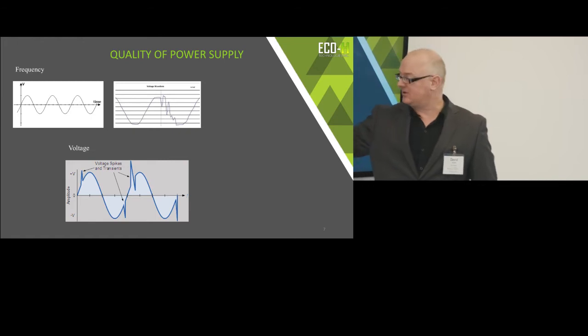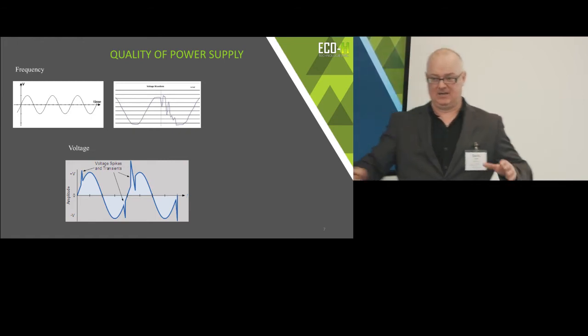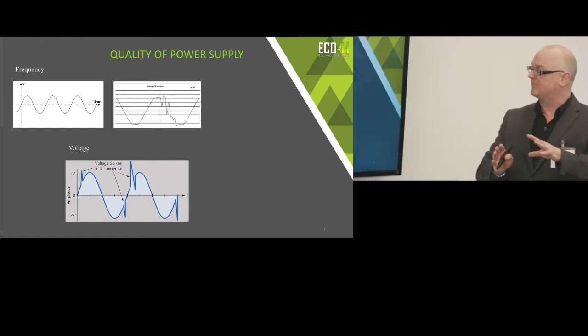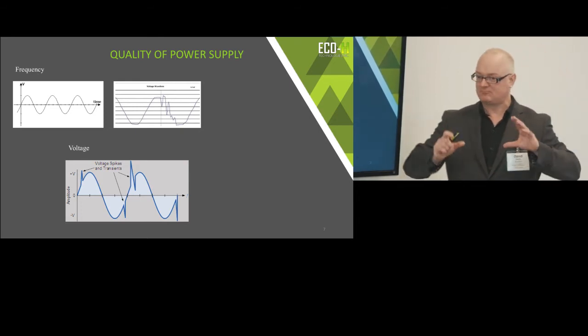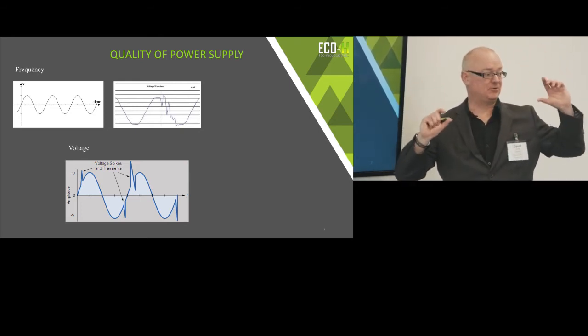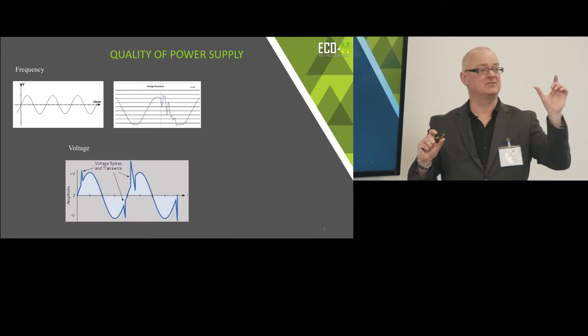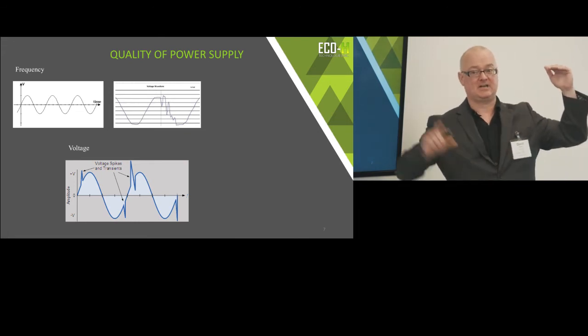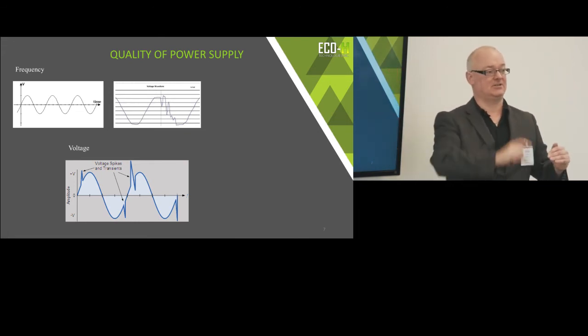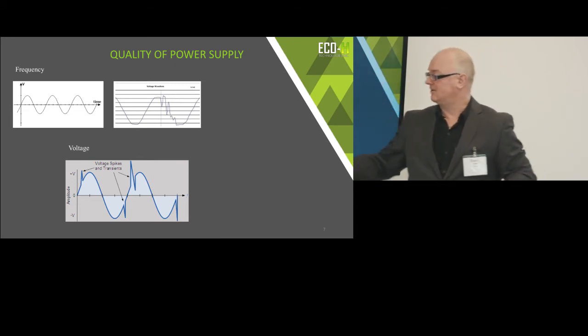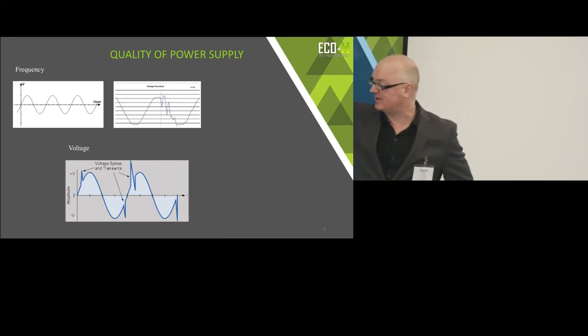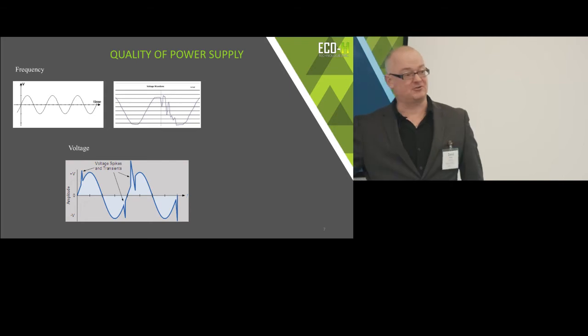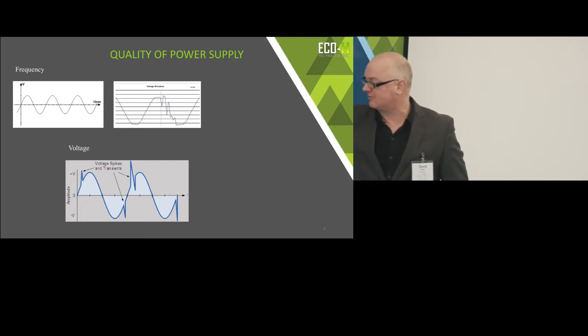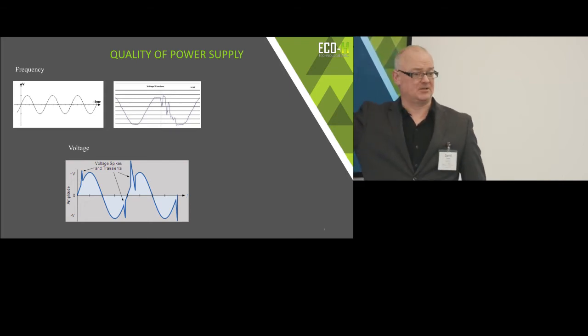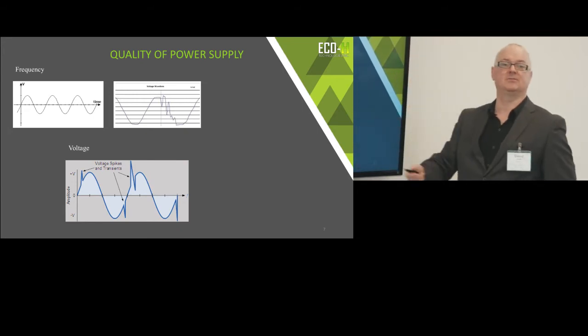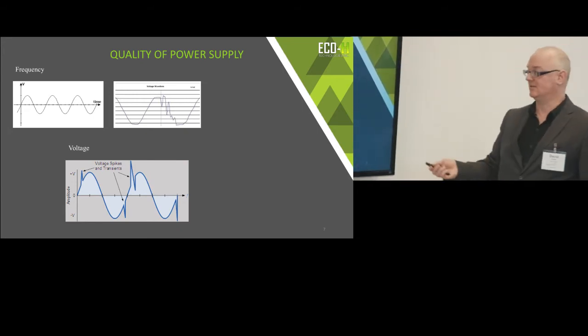Similarly with voltage spikes, we can see a huge voltage spike here. A little bit of math, just very quickly, because I won't bore you. Watts are proportional to voltage and current. So you can have a high voltage, low current, and have the same watts. You can have low voltage, high current, and the same watts. So you get the same output here, but because you get a spike in the voltage, that means your current could drop. Consequently, you could get a drop in the voltage, which means the current's going to spike. So again, that causes issues for hardware systems and VFDs and controls.